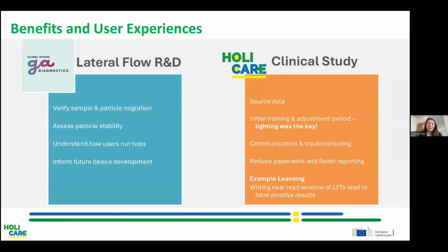Now we're going to move on to benefits and user experiences. From the perspective of a diagnostic company that made these lateral flows, having images of device prototypes used in the field actually provides valuable insights into test performance. It allows assessment of how well the sample and detection particles migrate across the read window. It gives us feedback on particle stability over time and ideas of how the users have performed the test, so a bit of an extra usability study for us.